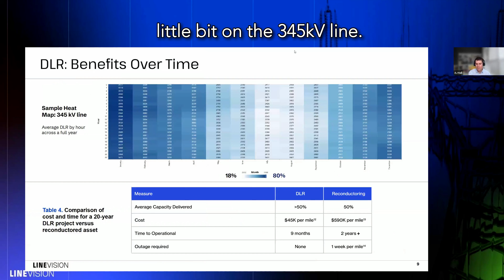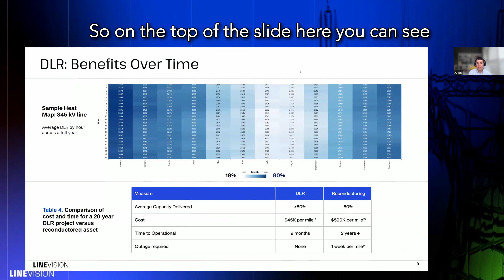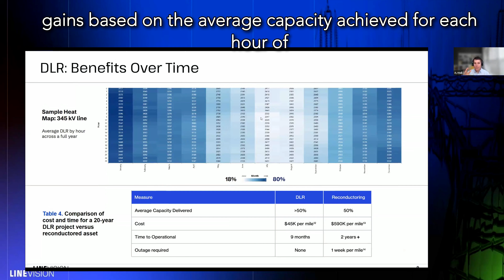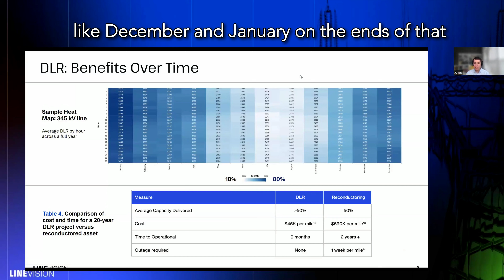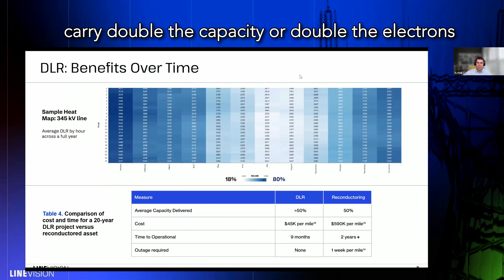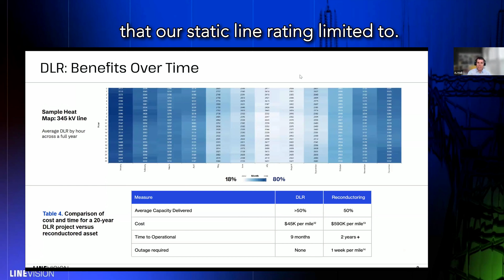Let's zoom in on the 345 kV line. At the top of the slide is a heat map showing the capacity gains achieved for each hour of the day across all 12 months of our deployment. In winter months like December and January, at the ends of the chart, there's a lot of capacity that can be gained—in fact, at times the line could carry double the electrons that our static line rating limited it to.